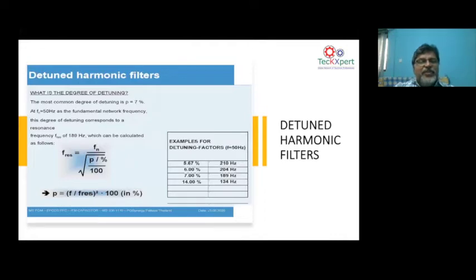This slide shows you how the detuning reactor has to be selected. As you go to higher and higher detuning factors, for example, the most conventional one everybody uses is the 7% detuned reactor, that is at 189 Hertz. 189 Hertz is a frequency that lies between the 3rd and the 5th, because the 5th harmonic is 250 and the 3rd is 150, so you are in a safe haven. You put a detuned reactor of 7%, you are keeping the detuning frequency between the 3rd and 5th, and so there is no amplification of harmonics. Similarly, putting a 14% means you are putting the detuning below the 150. You are putting the detuning between 100 and 150.